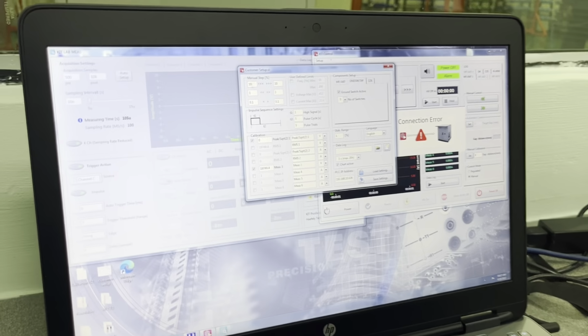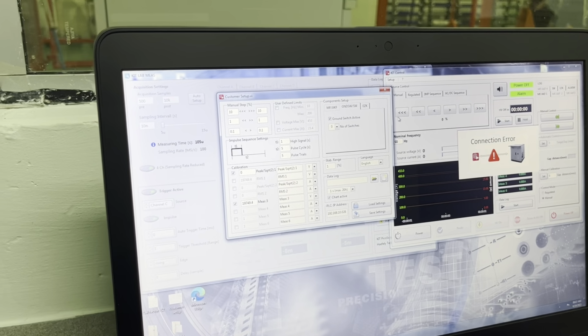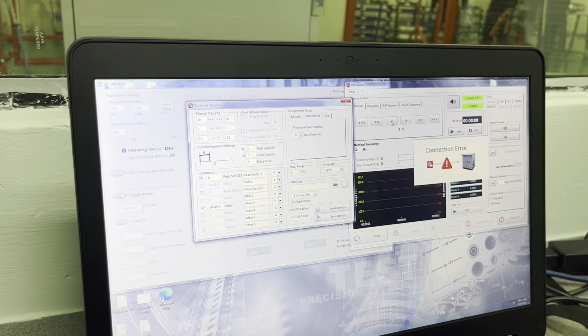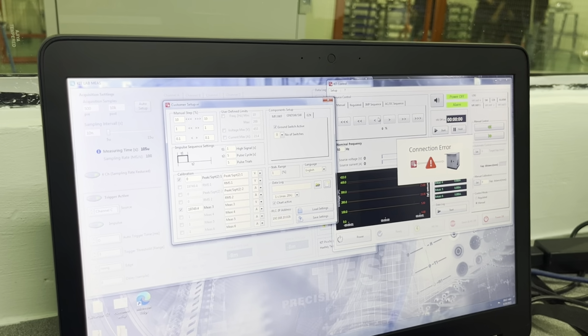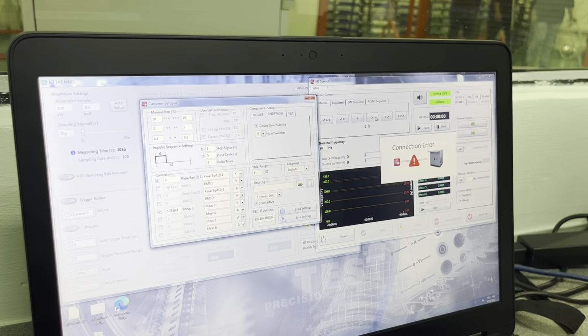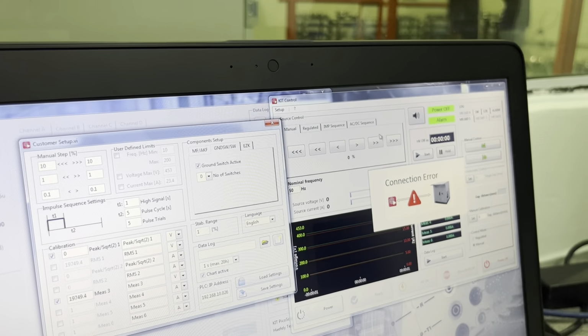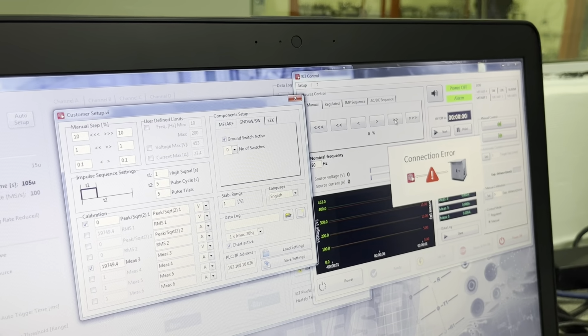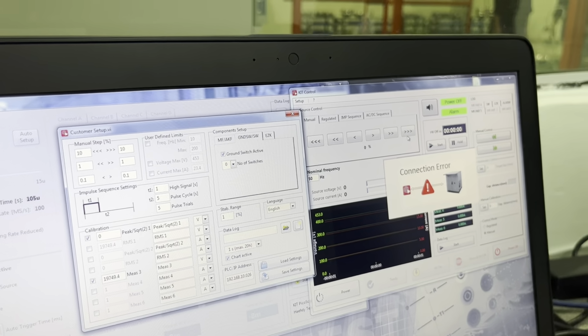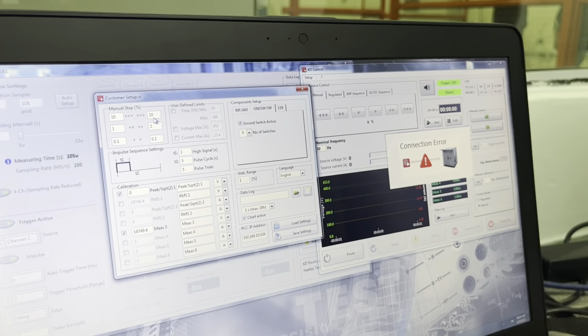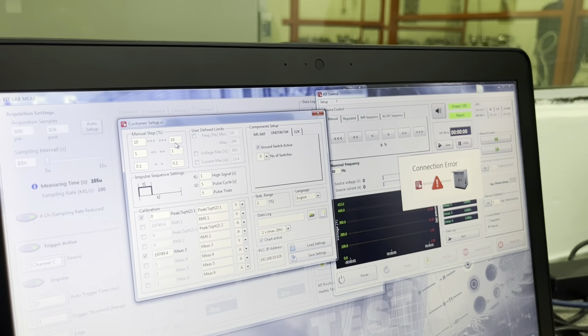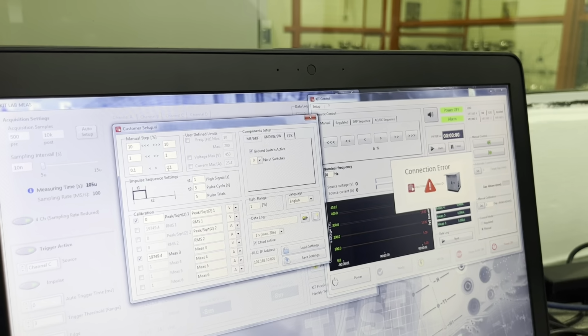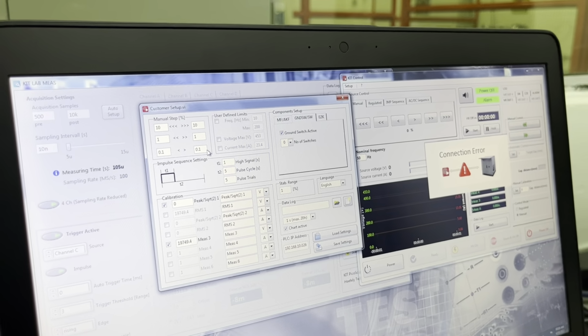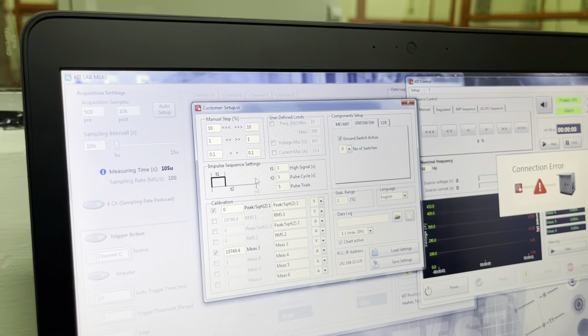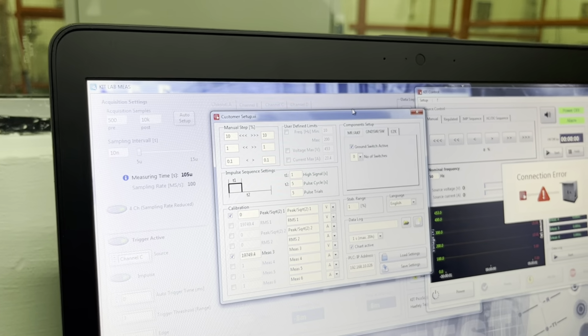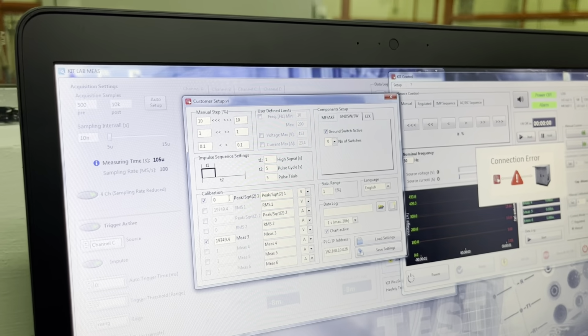This is manual step. Manual step will correspond to our sergeant, corporal, and private. So this is the least significant. The one arrow is least significant value. The double arrow is middle one, and the three arrow is the faster one. So we can set here how many steps we are going to change for every click. We can set it 10, 1 and 0.1 for precision. For impulse sequence setting, it will remain in default mode. Component setup will remain in default mode, and we are going to set up our calibration.